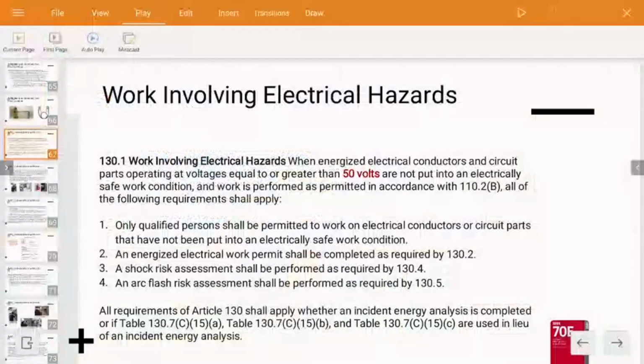Article 130 of the 70E is where we find the requirements to perform energized work. For the sake of time, I can't go over all these requirements. The key point you need to remember is that magic number, 50 volts. Notice again, it doesn't say AC or DC. If it's 50 volts or higher, all the rules like the planning we talked about apply. Okay? And only qualified persons are allowed to do that work. And most of the time, you have to have what's called an energized work permit too. That's part of our planning documented process. There are some exceptions to the energized work permit. Again, if we're going to test or troubleshoot, we don't have to have the permit, but everything else in our plan applies.